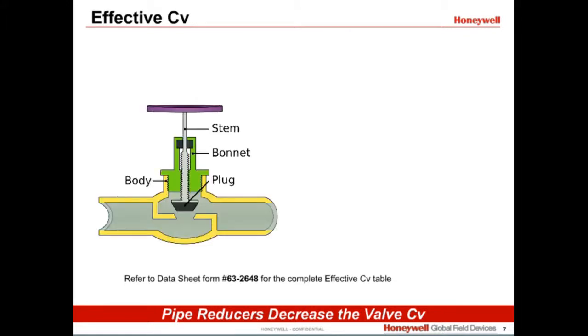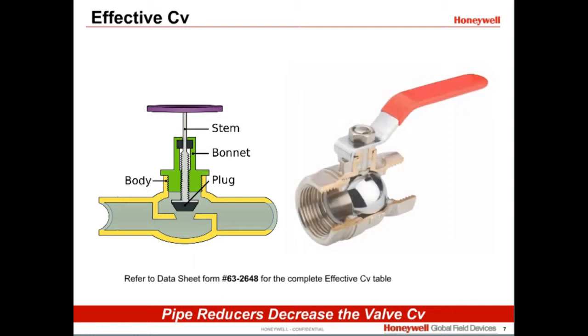Unlike a globe valve, the fluid flows straight through a ball valve. Therefore, for any given size, a ball valve will have a higher CV than the globe valve. So a smaller ball valve can provide an equal CV to that of a larger globe valve. This way, a lower-cost ball valve can be used in place of a globe valve.